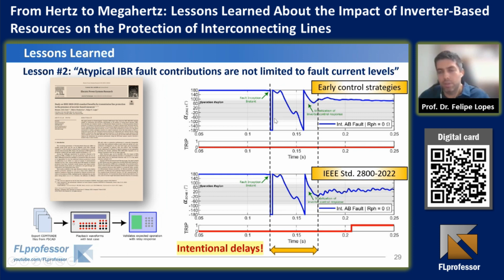doesn't disappear, because at the first moment of the fault, there is a transient state of the controls. This is the angle comparator used to apply the distance protection. And there is a transient state that we have to wait through, and then the controls stabilize. But depending on the control strategies, they can stabilize outside the operating characteristic or result in a very delayed operation. And using the new standards, when we inject the reactive current and the negative sequence current, we can see that they stabilize inside the operating characteristic. These results are available in this paper that we published recently.